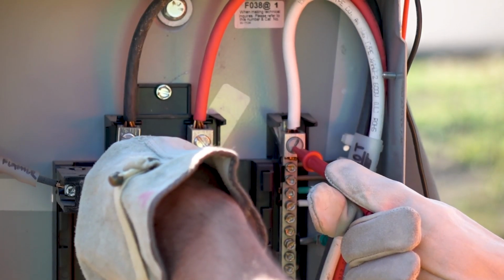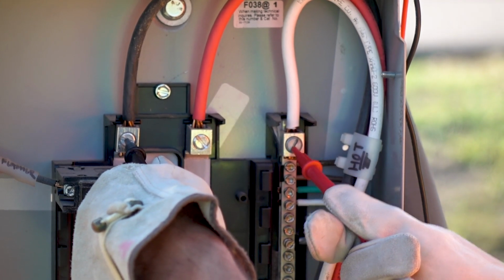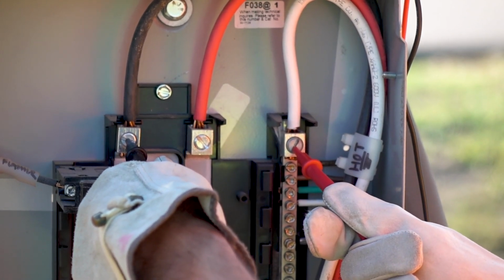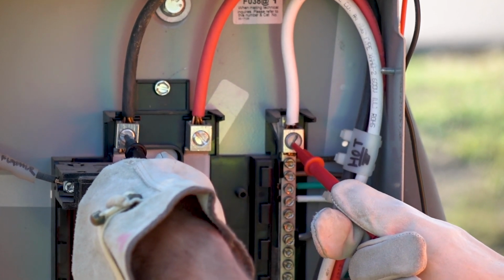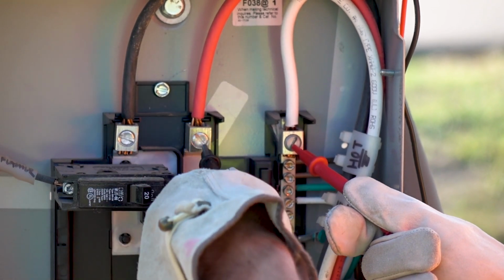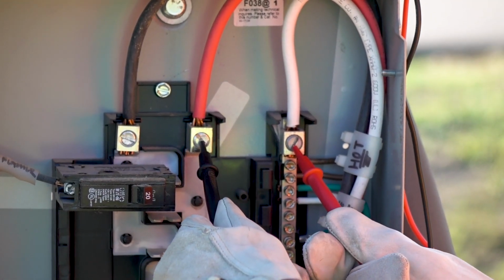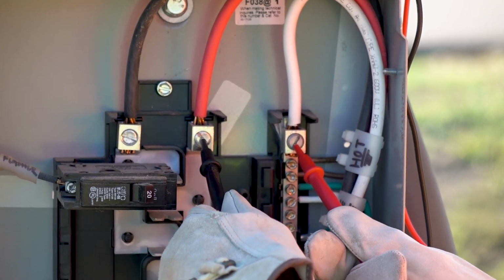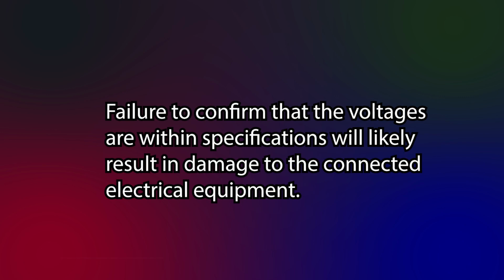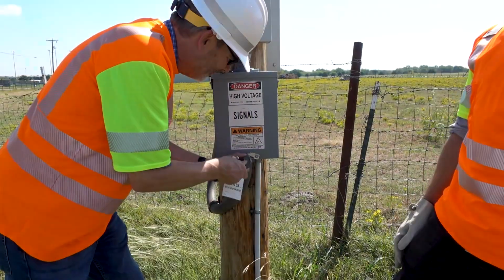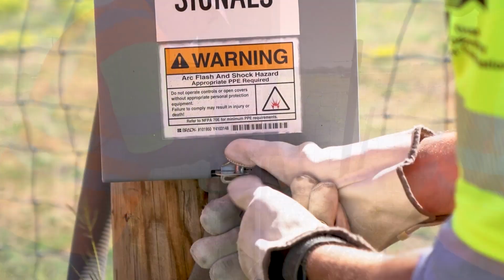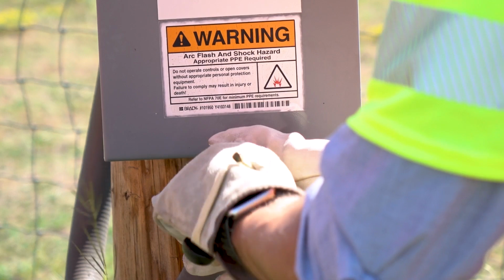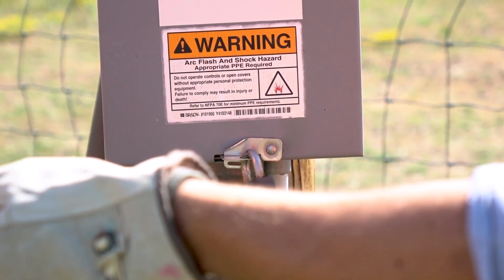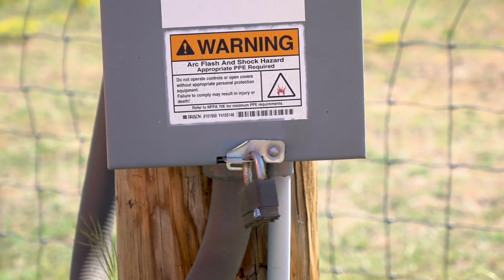If no voltage or a lower voltage is recorded for this reading, then it is likely the service has not been properly grounded. Should any of the readings be outside of the ranges shown, none of the breakers may be turned on. The serving utility must be contacted and changes made until the readings are within the correct ranges. Failure to confirm that the voltages are within specifications may result in damage to the connected electrical equipment. Once the issues have been corrected, the inspector should confirm the service enclosure is padlocked with a master lock keyed to 2195. This completes our review of the inspection tasks for a Type T electrical service.